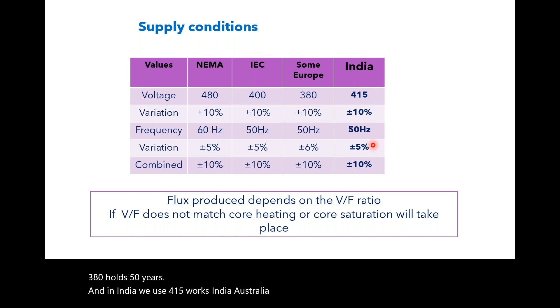IEC has 400 volts. Most of Europe has 400 volts: Germany, France, UK, and so on, at 50 hertz. Some European and some East Asian countries like Thailand and Indonesia have 380 volts, 50 hertz. And in India, we use 415 volts. India, Australia, New Zealand, we use 415 volts, 50 hertz, plus or minus 10%.